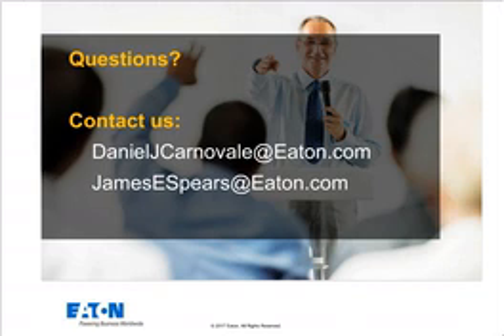That's good. Next question. Okay, can you discuss requirements for 4-wire input to UPS bypass with 3-wire loads? Another good question, and I'll try not to make the answer too long-winded. Keep in mind you can contact me or Dan directly at the emails showing on the screen now. But the question was, if I have a 3-wire service to the bypass, when would I maybe need a 4th wire or a transfer switch that operates with 4 poles? In other words, a pole for each of the 3 phases plus the neutral. And how does that impact the critical load?